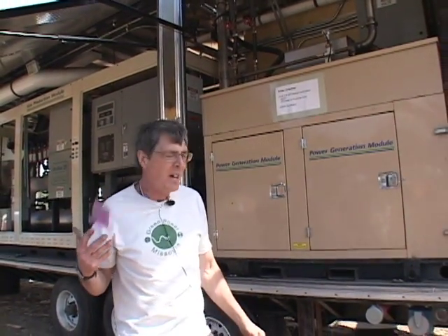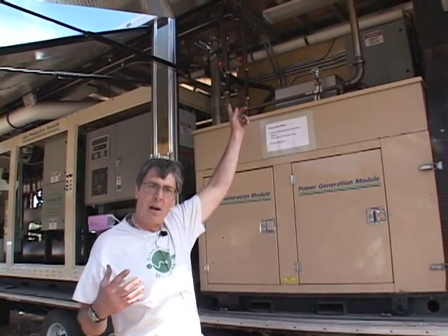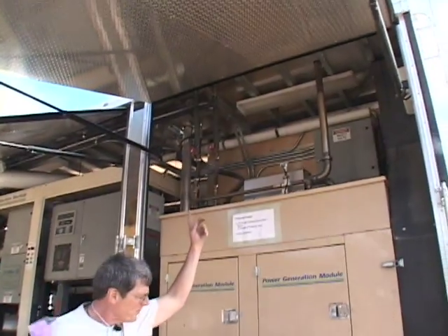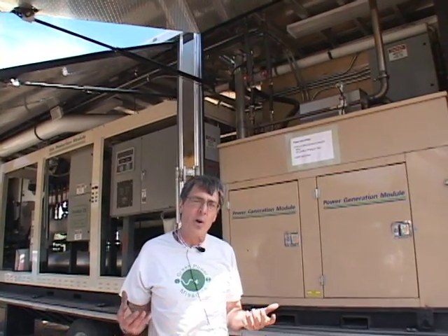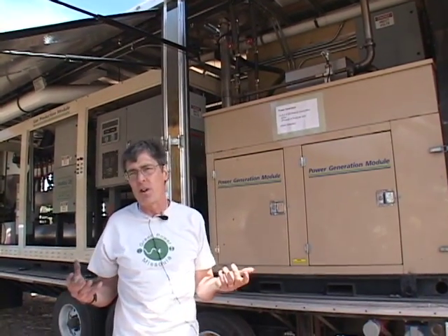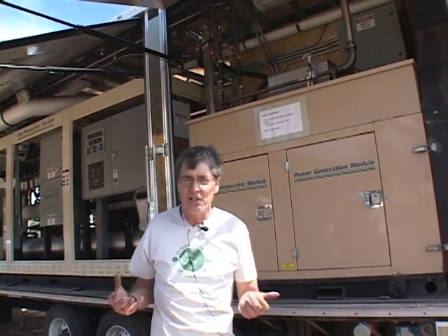Since we don't have electrical load right here, we're only running our parasitic systems, which run between 2 and 4 kilowatts. So we have additional gas that's left over. What we do is we flare it up this top in the stack. We do have an onboard transformer, and I can transform that 480 three-phase into 208 three-phase, and from that we can get 120 single-phase, which would power normal household appliances.